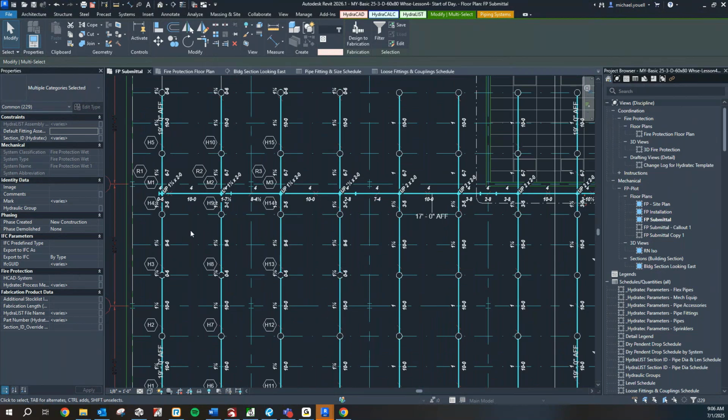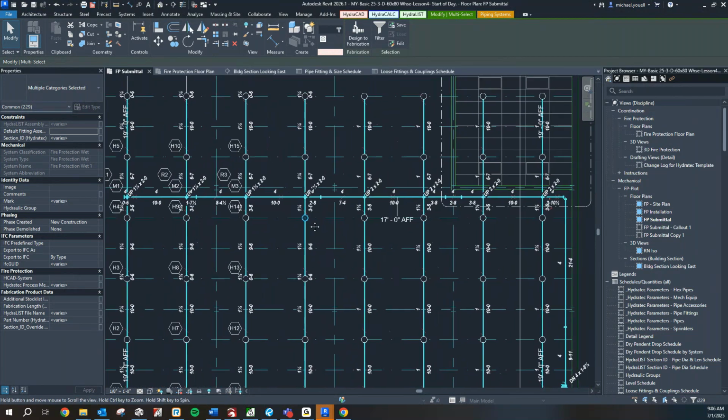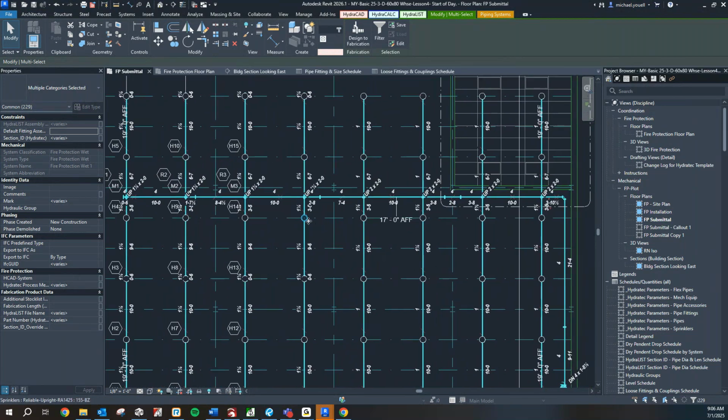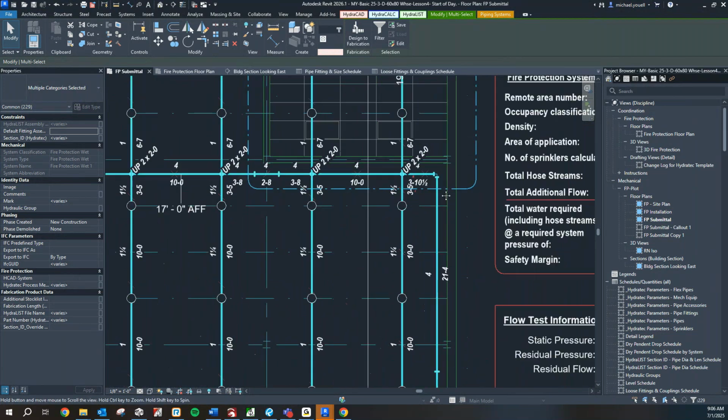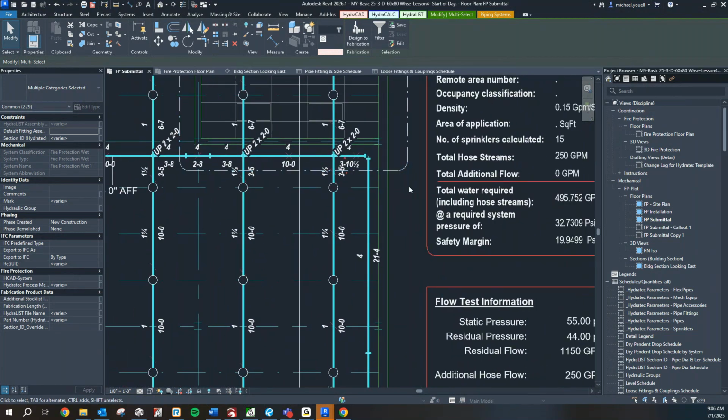And the main on the right end of this, where the main and where the cross main and the feed main come together. So Dave, do you see that first piece is 4 inch, 3 foot 10.5? Yeah, I do. That's the center to center. That's from the center of that pipelet to the center of the feed main. And if we take out about 4 inches, what would be left is 3 foot 6.5.